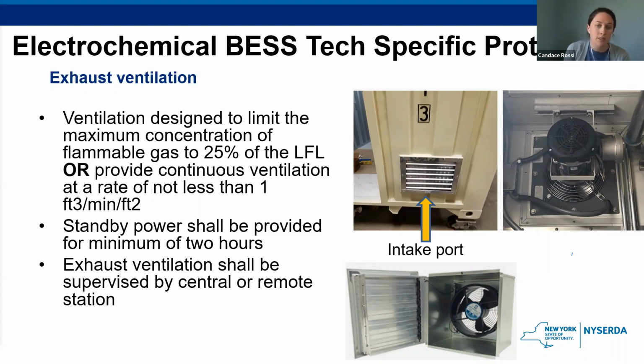So the ventilation needs to be designed to limit the maximum concentration of flammable gas to 25% of the lower flammability level, or provide continuous ventilation. There needs to be standby power for at least 2 hours and needs to be supervised by a remote station. Will likely also be part of the battery management system. And it may be required for lithium ion as a method of explosion control, which we'll discuss in a few slides. It may be required for a responder to remove flammable gas due to a thermal runaway event. So the turn on switch should be remote from the system, and signage should always be used to direct the responders to the ventilation fan.